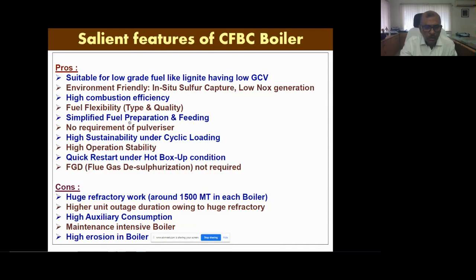and other operational parameters. For fuel preparation, there is no milling plant and no requirement of pulveriser. It is highly sustainable under cyclical loading because heat is absorbed in the mass in the combustor, so this helps in the operation. Quick restart in hot box condition and flue gas desulfurization are other advantages. The disadvantage is that each boiler has around 1500 metric tons of refractory. This causes major issues during startup and shutdown of the unit, and during maintenance activities for taking up any maintenance work, and this has resulted in high unit outage duration.